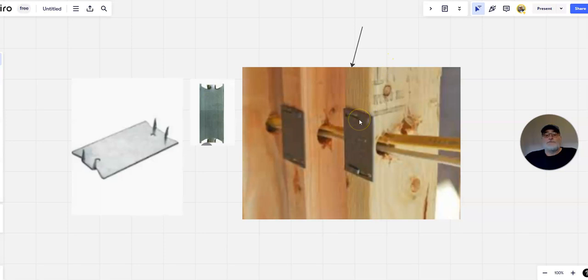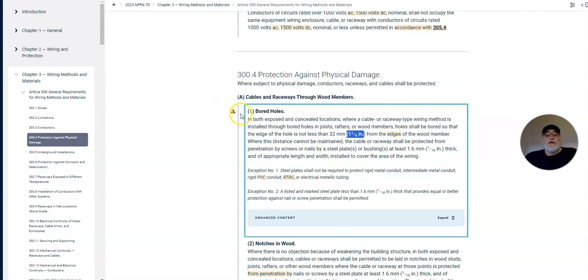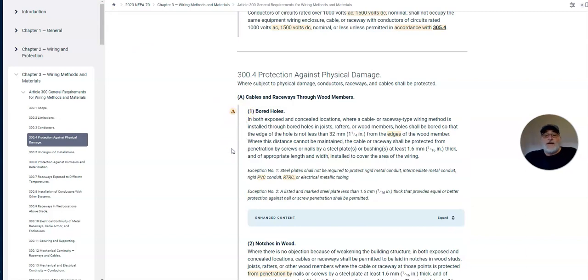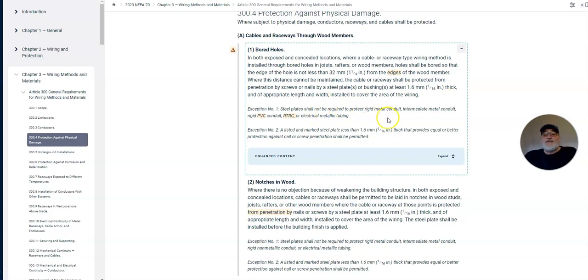Right here is what we're talking about. Pretty simple. Okay. There's an exception. Steel plates are not required to protect rigid metal conduit, intermediate metal conduit, or IMC, rigid PVC conduit, RTRC, or electrical metallic tubing. Okay, EMT. So you literally could run EMT in those walls and not have to worry about the nail plates. Exception 2 here: a listed and marked steel plate less than 1/16 of an inch thick that provides equal or better protection against a nail or screw penetration shall be permitted.